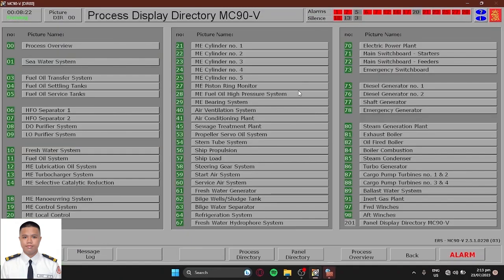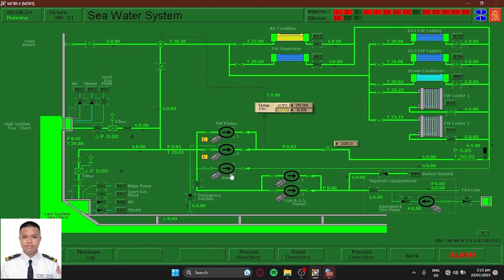Next step is to check our seawater system. Notice how our aux pump turned off and the pressure is now low. So what you're going to do here is turn on the main pump here. Wait for the pressure to rise up. There we go. So auto the temperature control, remote these pumps, and turn these two valves on.